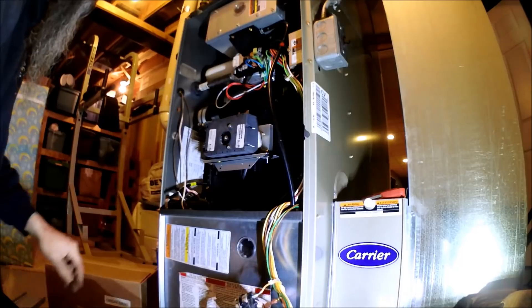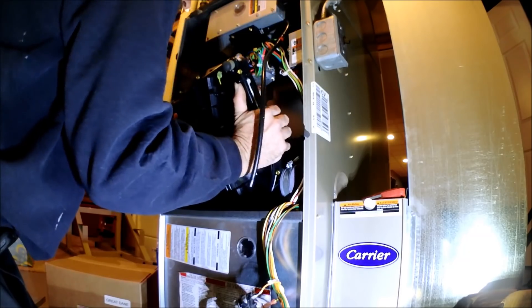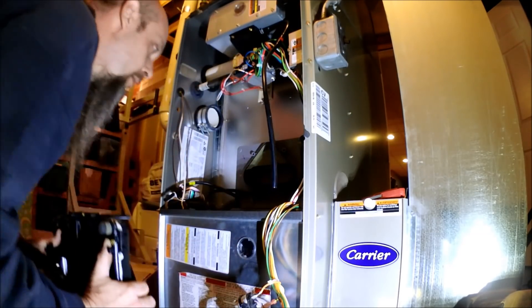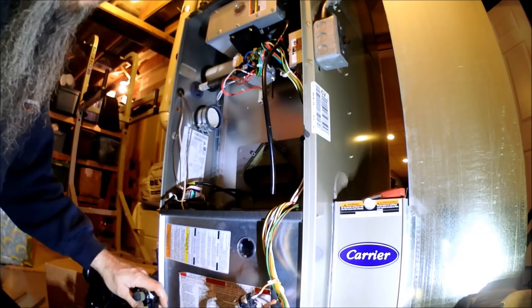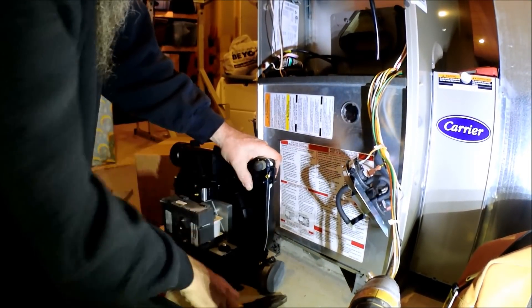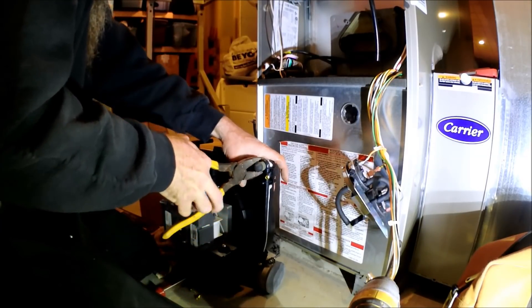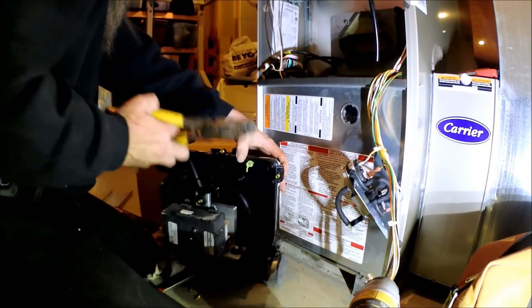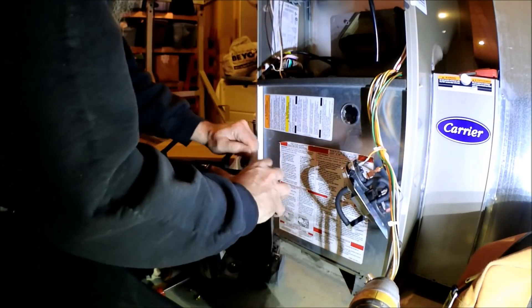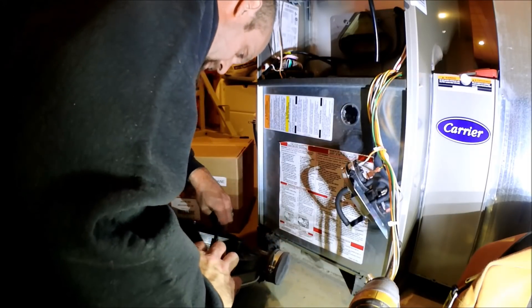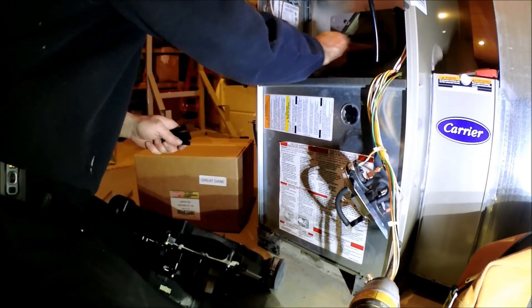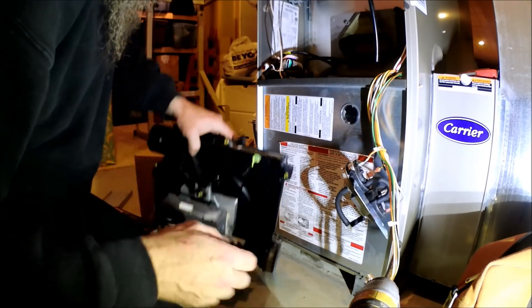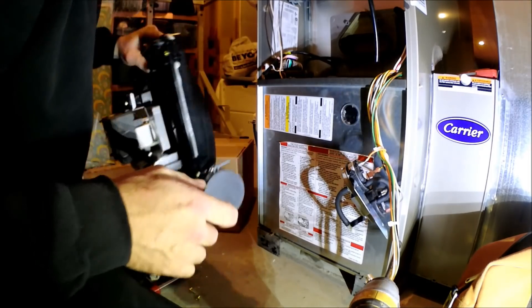One thing you've got to remember - just taking a good whiff here - one thing you've got to remember is that cap. This cap does not come on the other inducer. Also the standoffs. The standoffs don't come on the other inducer, so you've got to make sure to take those out.